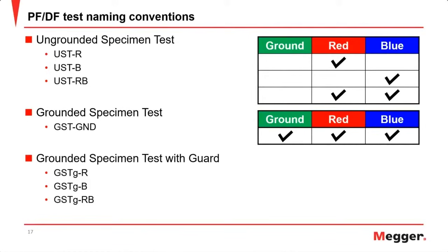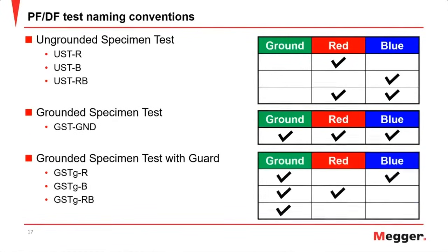So in all three of these cases, you will be measuring the current to ground. But when you have guard R, you will not measure the current on the red, but you will measure the current on the blue. The opposite for guard B, where we're guarding out the blue. And then finally guard RB, where we only look at the current that comes back on the ground channel. So very important to keep this in mind as we go through and talk about the next test that we have.